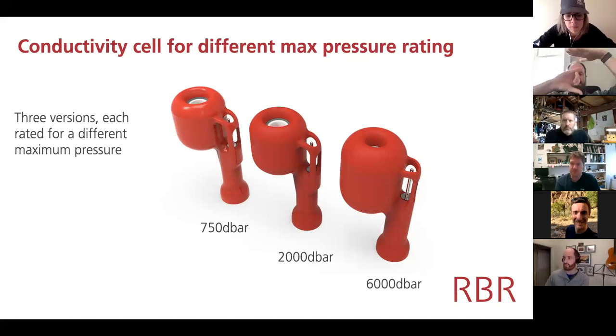By 10 centimeters, it has changed by 10 milli PSU, which is the Argo spec. So that's the number that we most often quote, because it's usually in talking to Argo scientists. How close can you get to the surface and still be within the Argo spec? It's 10 centimeters. But actually, the more correct answer is 15 centimeters if you need 3 milli. Now, lots of other things factor into that and make that an implausible measurement case.